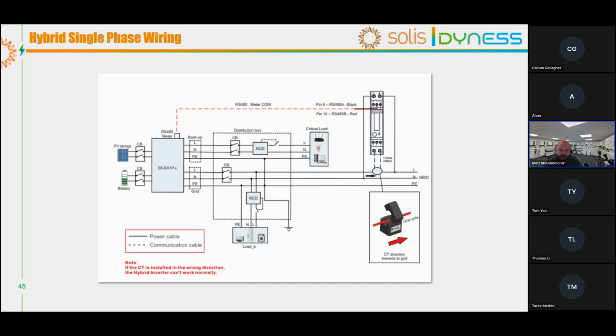What's also hugely important is the direction of the CT. If you don't have the CT in the right direction, then your inverter logic will not work properly because it will be reading the wrong values. For example, instead of seeing export through the day, it would read export at night when you're actually importing energy, because the CT is round the wrong way. So it's hugely important, and if that CT is round the wrong way, it's not going to operate properly.